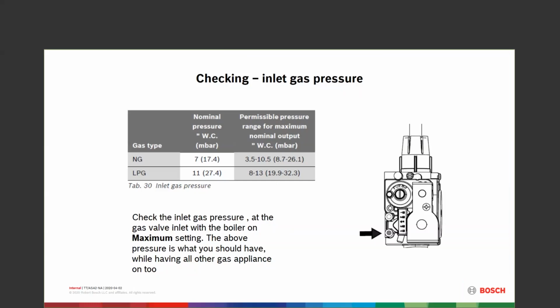So your inlet gas pressure, first thing you're going to check. Make sure you've got it. Make sure it's there. Make sure it's turned on. We've had guys, I had a call from the tech support. Guy told me gas was fine, everything's good. I said, listen, humor me. Go out and get your manometer. Let's see. He says, no, I'm telling you right now, it's good. Okay, it's fine. If it's good and it's fine, everything should be running. Well, he went out to get his manometer, and I happened to be hanging on the phone with him. And as he walked by the gas meter out front, he said, there's a lock on the gas meter. They must not have paid their bill. Well, he just told me it was fine.